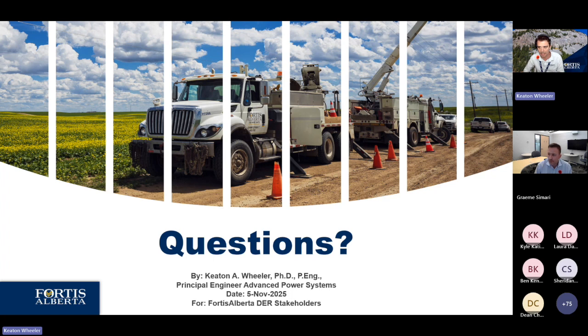And if the voltage is too low, it'll try to raise the voltage, so it'll inject reactive power to do it. But again, it's more dynamic than what you'd normally see. So if you're tripping frequently on overvoltage, generally speaking, you should start seeing that it'll absorb reactive power based on what the voltage is doing. The idea behind this is to get fewer nuisance trips, on top of the other benefits, which are more stable voltage and a reduction in regulator tap operations.